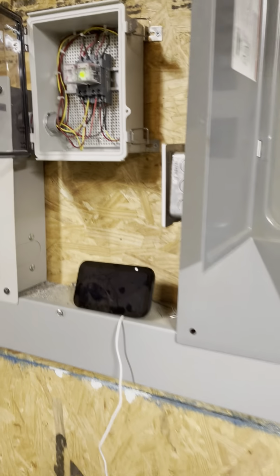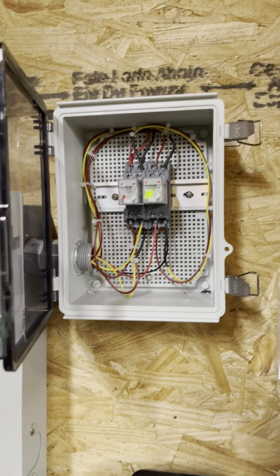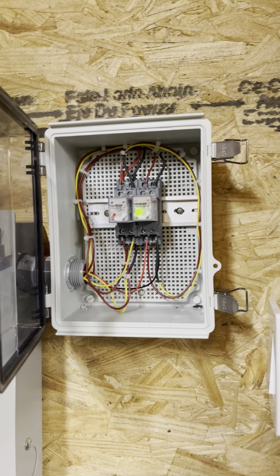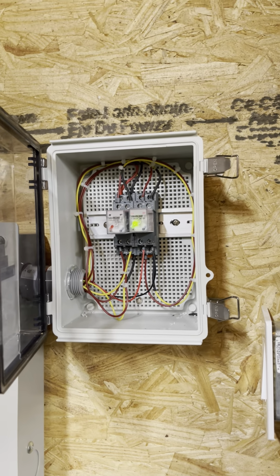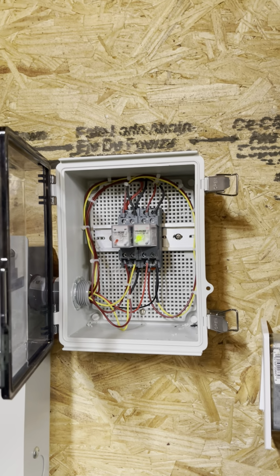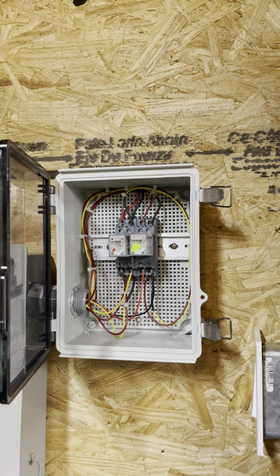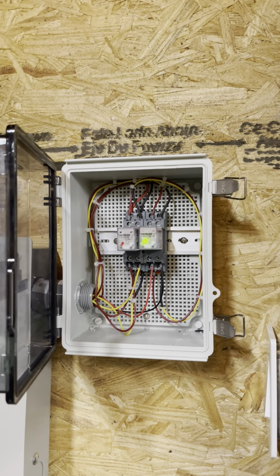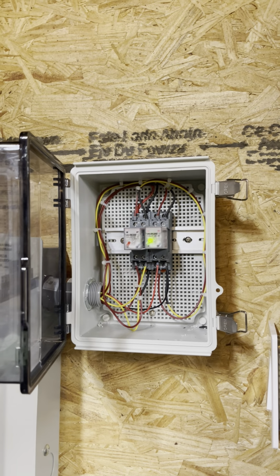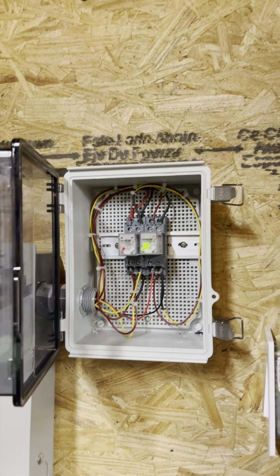So one of two things will happen. It will run long enough to charge the batteries up to that 55.3, which I'm not going to sit here and make you watch. When it does get to that set point, it will shut off and the generator will shut down, or the power gets restored. And if the power gets restored, I'm going to restore the power.